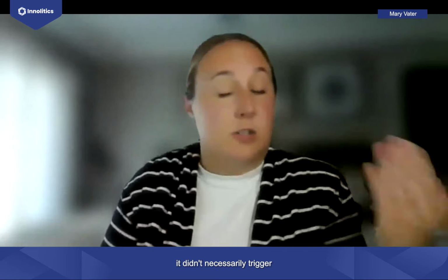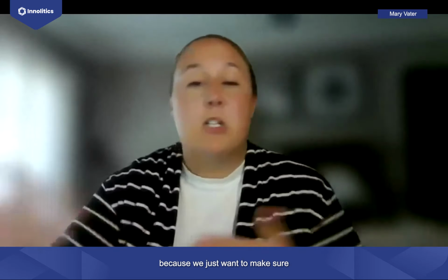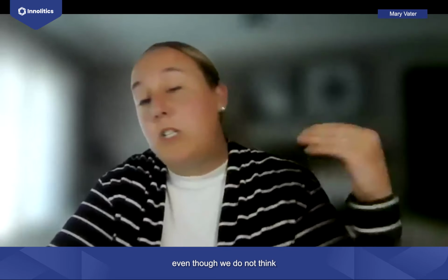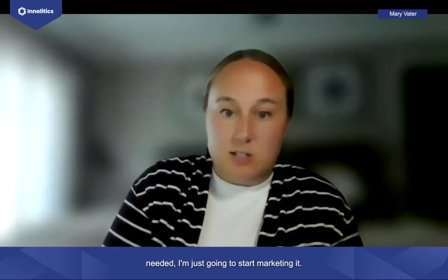It didn't necessarily trigger a 510K, but we're doing one anyway because we just want to make sure that the FDA is still okay with the changes that we've made, even though we do not think it triggered a new submission. So I've seen that too, where companies will decide, oh, it's probably not needed, I'm just going to start marketing it, but just to be safe, I'm going to still submit a 510K. So yeah. I think another thing too, if you think about it, right?